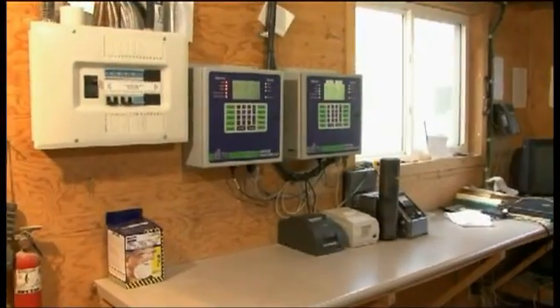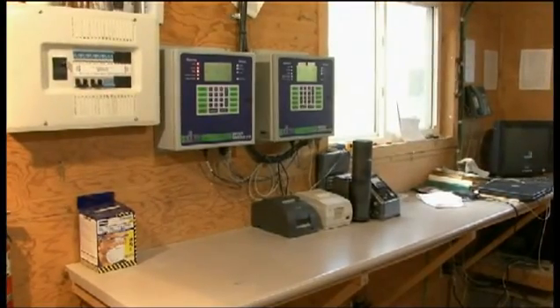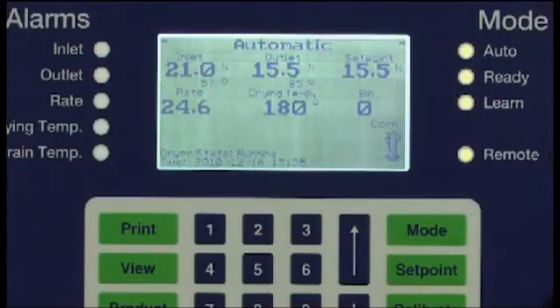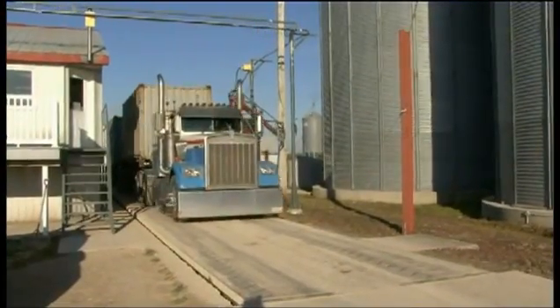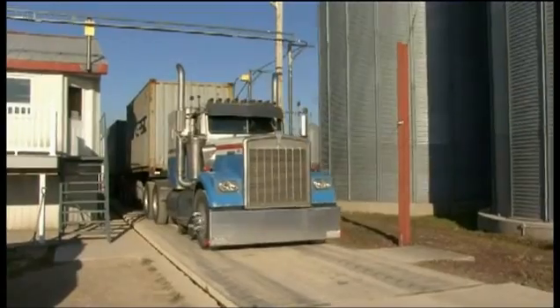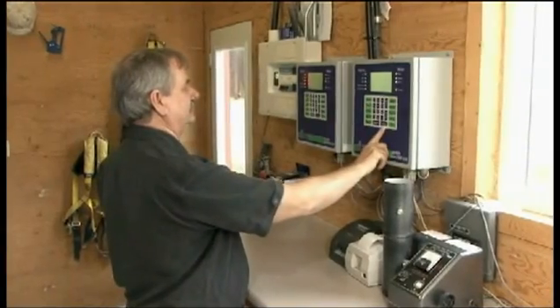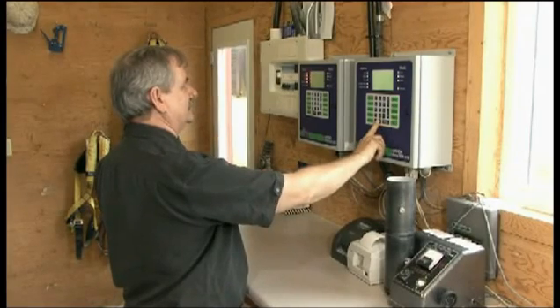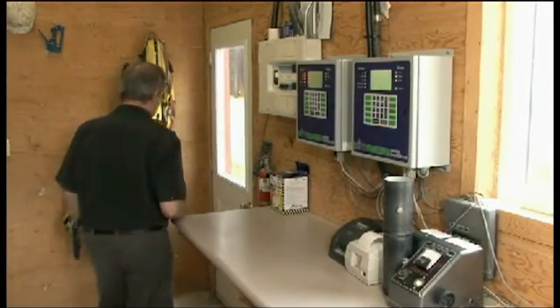With this information, the Dryer Master does not have to wait to react to changes in the outlet moisture. It is able to adjust the discharge rate as the incoming moisture changes. So, for example, as wetter grain comes into the dryer, the Dryer Master can begin to slow down the discharge rate just as the wetter grain reaches the hot zone. As well, if you increase or decrease the drying temperature, the Dryer Master will adjust the discharge rate to accommodate.